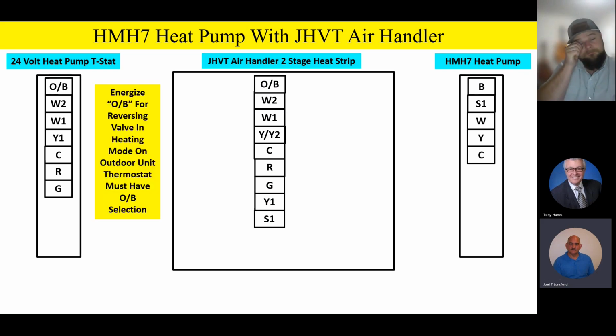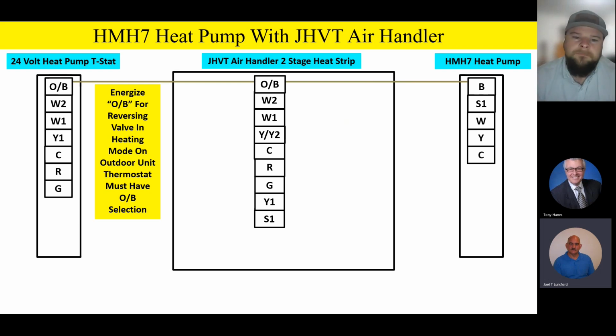So there's that OB signal. And again, it's going to be going to the B terminal outside. So OB to B to OB and then to B outside. And that's a reversing valve operation in the heating mode of operation. So remember that thermostat has to have that BO selection because we're going to energize the B terminal or the BO terminal on the heat pump thermostat for heating, reversing valve for heating. Very, very important. After that, it's pretty straightforward.